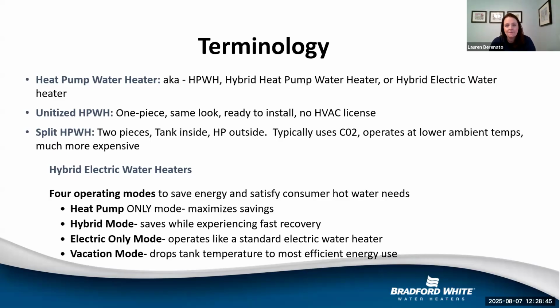Now, I like to talk about hybrid electric water heaters because for heat pumps, this is something that we really see. I mentioned this a little bit earlier, the 4 different modes that you often see with heat pump water heaters. For heat pump only, that will maximize your savings. For hybrid mode, that will save you money while also providing faster recovery. The heat pump recovery is very slow, it can be 10 hours or greater to fully recover your tank. For electric, it operates like a standard electric water heater. And then last is vacation mode, so that will drop your tank temperature down. We often see it at 90 degrees Fahrenheit.